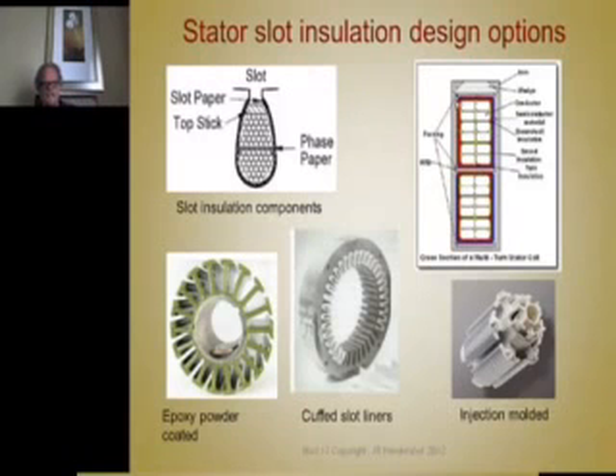Here's an example of a higher voltage machine that has open slots. See, your slots are open, and so you have heavy insulation around the outside, and you have a big thick separator between the two phases, and then it's wound with rectangular conductors that are layered in there. So this is very high slot fill, good thermal situation, and in here they insert an RTD, a temperature sensor, to monitor the winding temperature so it doesn't overheat.